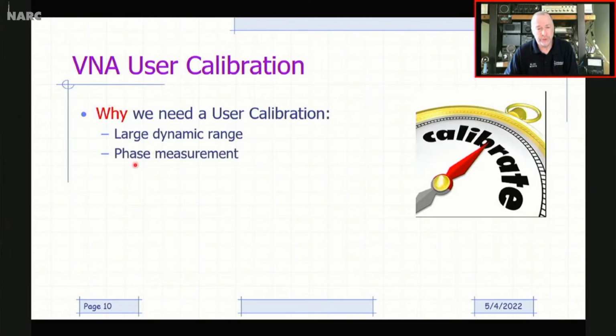Another reason is that we're measuring phase. Now, remember what I said about phase a couple of slides ago, is phase is really another way of measuring delay. So if I'm connecting a device up to my VNA, I might be using a short jumper piece of coax or a piece of wire or something to connect up to the device I'm trying to measure. There's going to be some delay associated with the signal going through that interconnect. And we might want to remove that so that it doesn't become part of our measurement, because the delay or the phase of that interconnect is not part of the DUT. So we want to remove that.